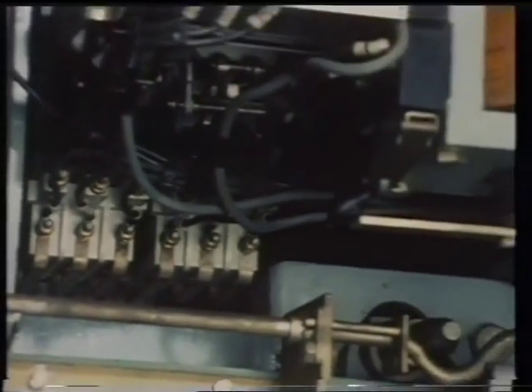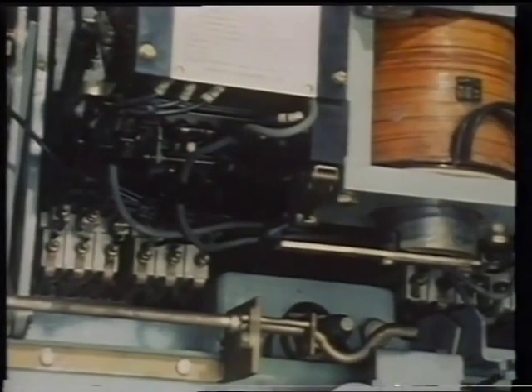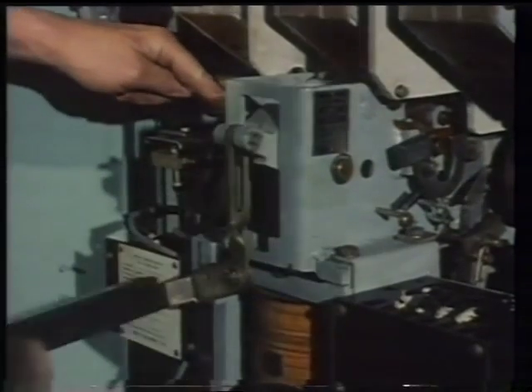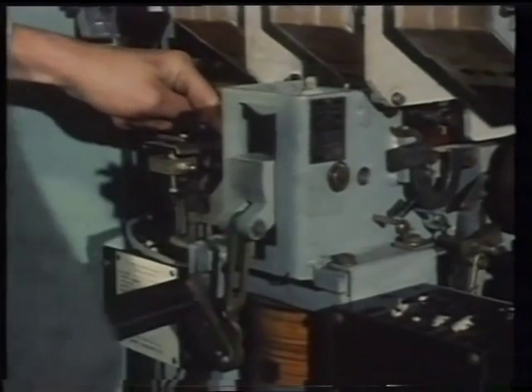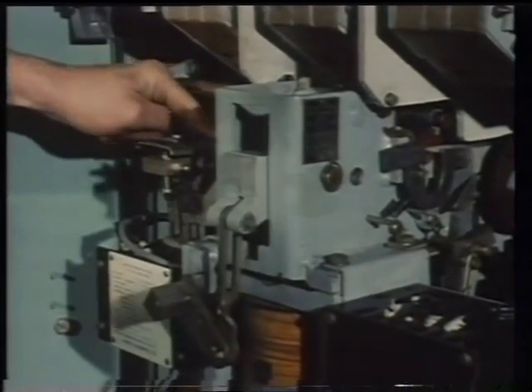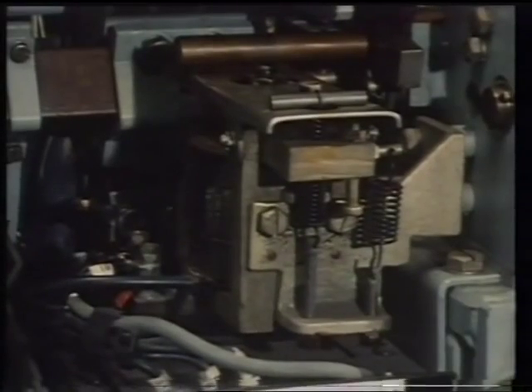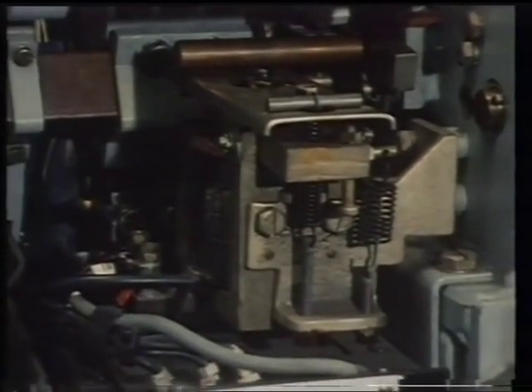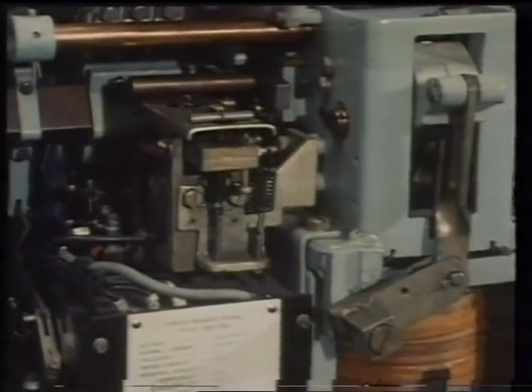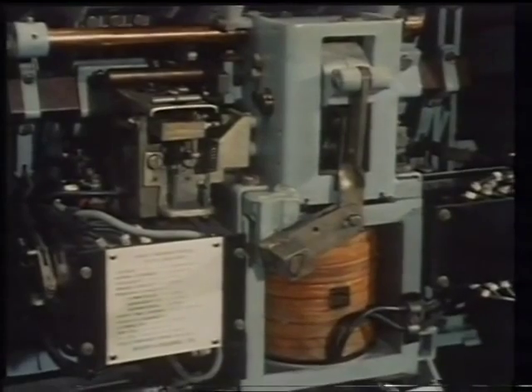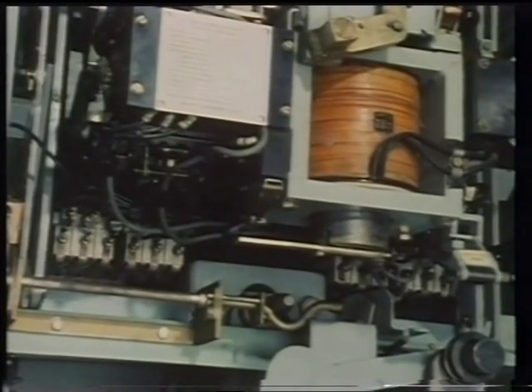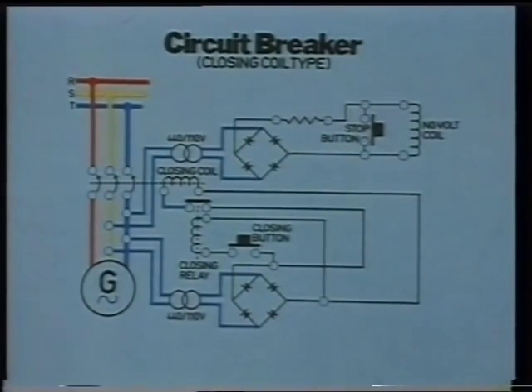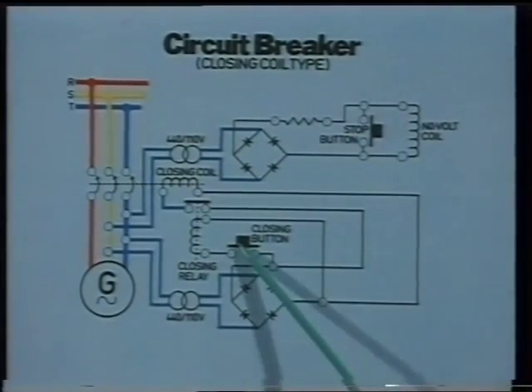There is a set of spring-loaded plugs at the rear of this circuit breaker. Check that they are free-moving and connect properly. Test the no-volt trip and the closing mechanical linkage by holding the no-volt armature down, closing the breaker manually and letting the trip go. If the breaker fails to close, the most likely causes are a loose connection, a sticking trip button, or the overcurrent or reverse power trip contacts not resetting properly. Alternatively, an open circuit fault has occurred in the closing coil circuitry or due to malfunction of the power supply to the closing coil.